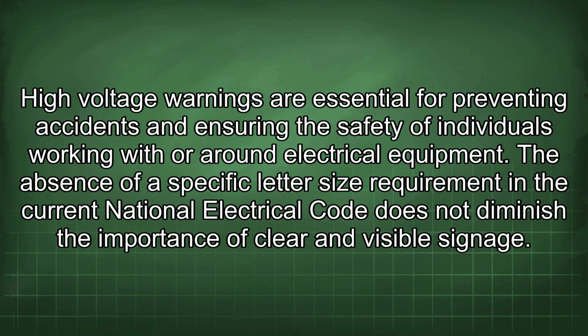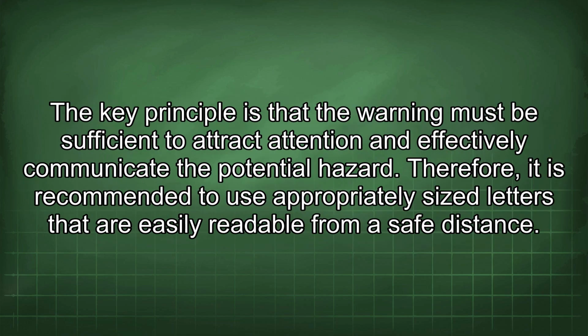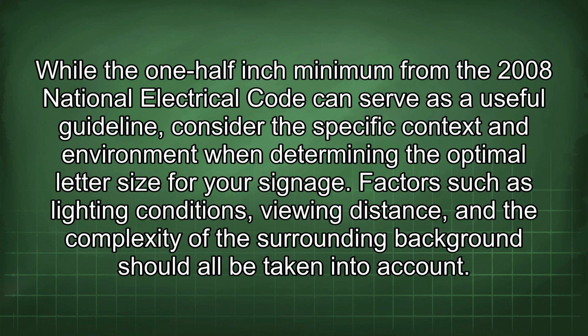The absence of a specific letter size requirement in the current National Electrical Code does not diminish the importance of clear and visible signage. The key principle is that the warning must be sufficient to attract attention and effectively communicate the potential hazard. Therefore, it is recommended to use appropriately sized letters that are easily readable from a safe distance. While the 1/2 inch minimum from the 2008 National Electrical Code can serve as a useful guideline, consider the specific context and environment when determining the optimal letter size for your signage.